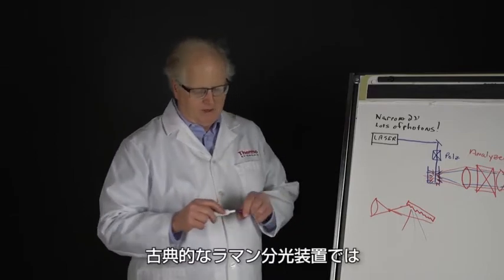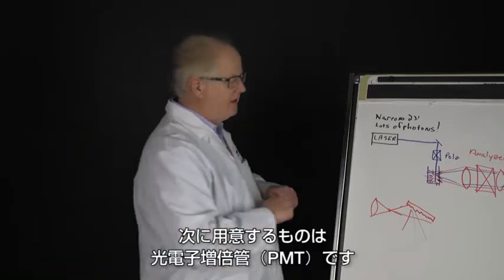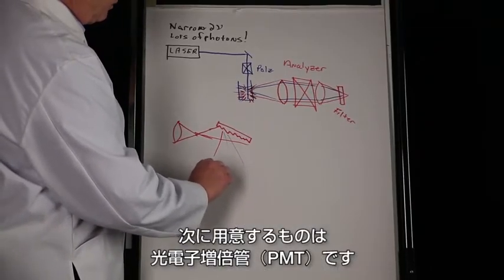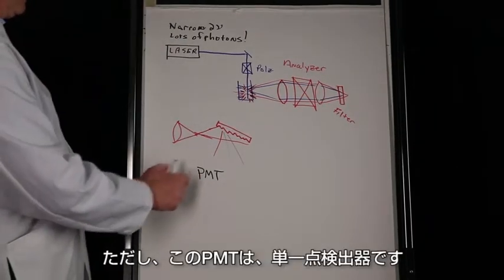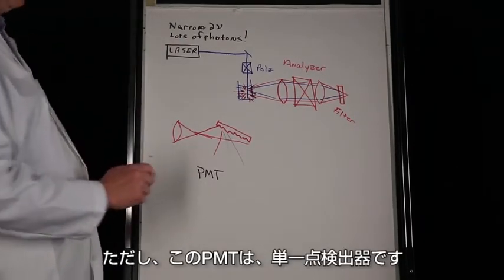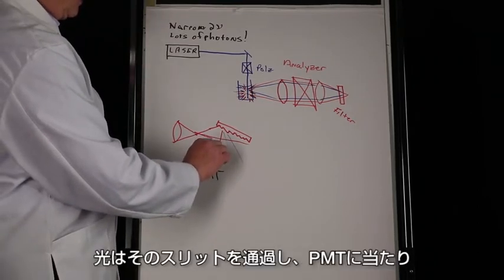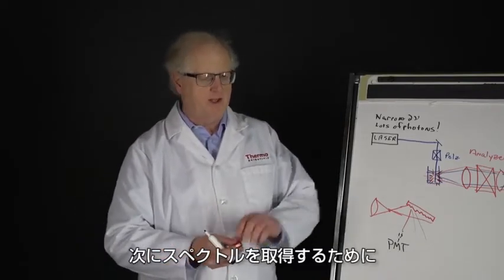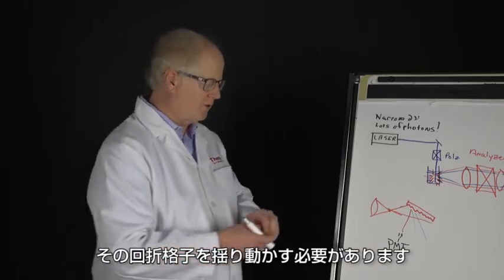Now in a classic Raman spectrometer what I would then have is a photomultiplier tube (PMT), which we'll describe a little bit about how that works in the next video. That PMT however is a single point detector, so you would have a slit, a narrow slit. The light would travel through that slit, hit the PMT, and then in order to take the spectrum you would have to rotate the grating - you have to rock that grating around.